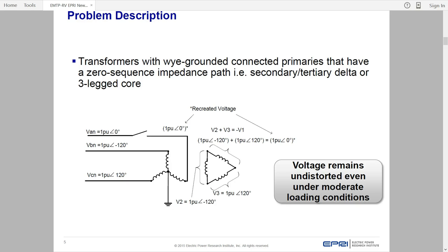and so basically becomes equivalent to your magnetizing impedance when you're sitting there with no load. So we actually did some testing at TVA on a station auxiliary transformer. We tested at no load, a light load, and actually medium load, just to show where we worked on all those operating scenarios, and we were able to detect an open phase. And again, it was able to detect it on the no load case.